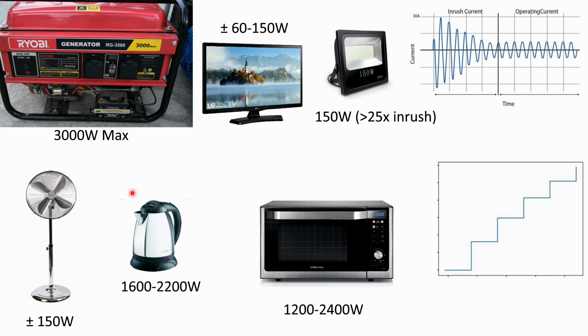When plugging in your appliances, just be mindful of the maximum power output of the generator. For example, this is only a small appliance, but in terms of its power consumption, it's very high for its size. It has a heating element which consumes a lot of power. If I plug in this kettle into this generator, it will load this generator heavily. Just because the generator says 3000 watts does not mean that the generator can provide a continuous output of 3000 watts. Most generators used in domestic applications should not be loaded more than 75%. So in this case, a 2 kilowatt kettle is close to the maximum continuous rating of this generator.